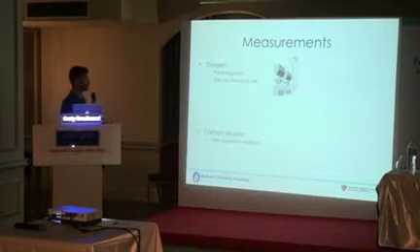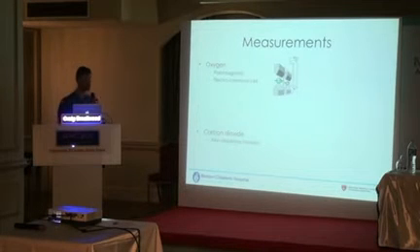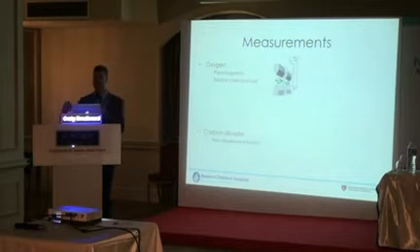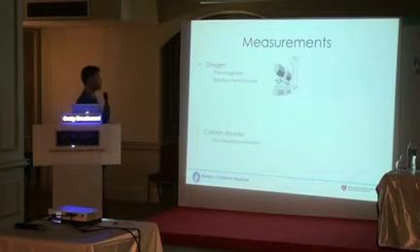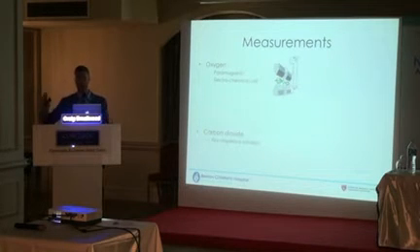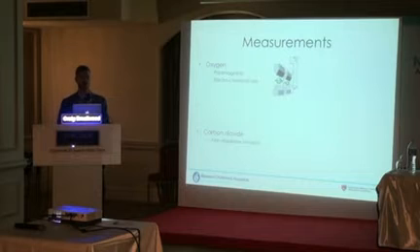So let's talk about a little bit of technical overview of how we're going to measure these things. So this is an oxygen sensor. I'm going to talk about 2 different technologies, paramagnetic. This one's really cool. So what's really interesting about oxygen as a gas is it's paramagnetic, and it has a tendency to be attracted to a magnetic field. So what happens is if you have a device, so a GE ventilator, for instance, that has a gas exchange module right in the side, this is the technology that's incorporated there.